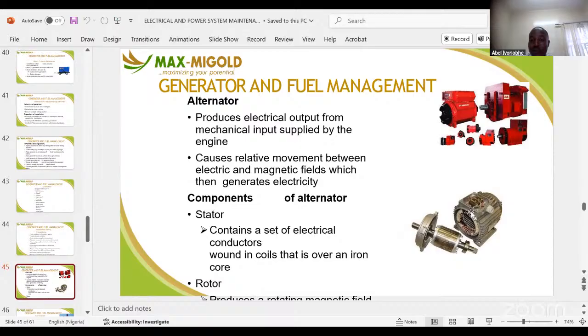So when you service and the generator still goes down, maybe it is because of overuse or overloading. So you have your record. This generator is designed to carry 4 AC, and we are using it for 5 or 6 AC. You manage expense. It might work now, but in a short while, it's going to break down.